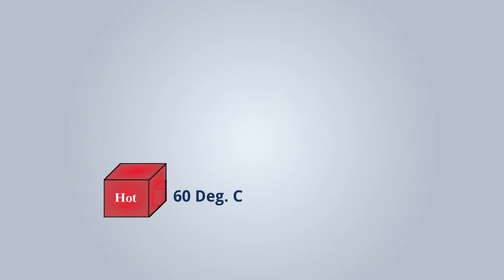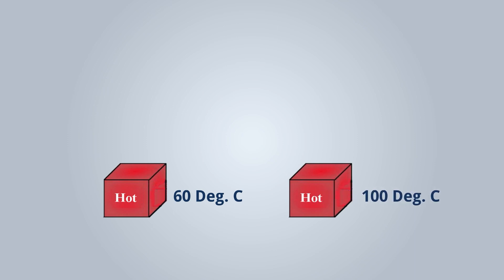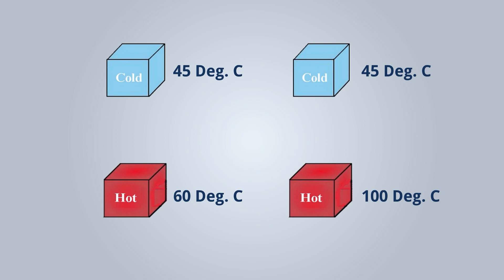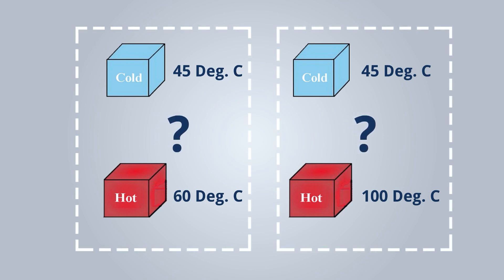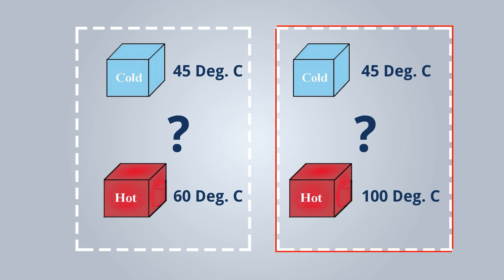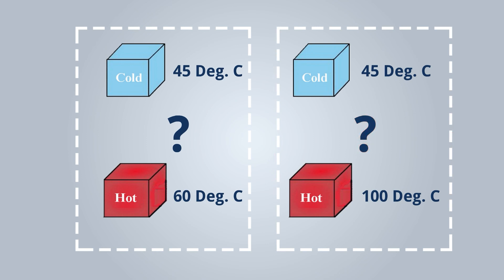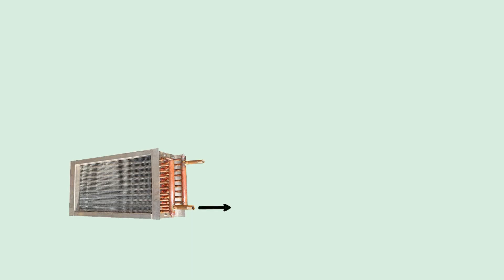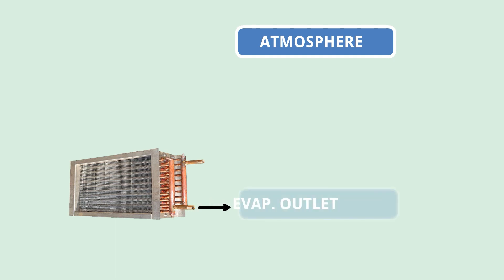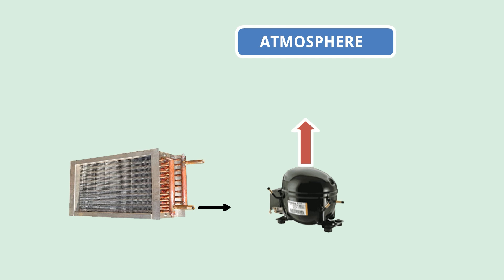Consider a hot body at 60 degrees centigrade and a cold body at 45 degrees centigrade versus a hot body at 100 degrees centigrade and another cold body at 45 degrees centigrade. Heat transfer will be faster in the second case because the temperature differential is greater. The evaporator outlet temperature is lower, and we need to remove that heat to the atmosphere. The compressor increases the temperature and pressure of the refrigerant — increasing the temperature differential — and helps to remove the heat. The compressor will not remove the heat directly, but it helps to remove it.